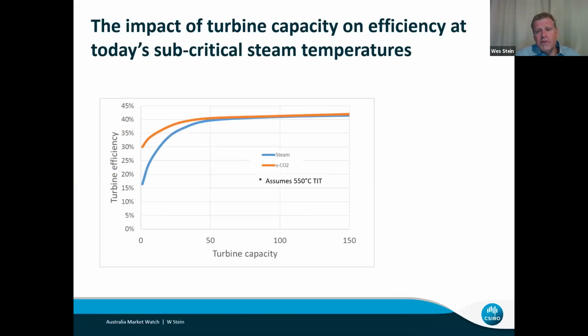One of the reasons we're interested in this supercritical CO2 cycle is that much of Australia's CSP market lies towards the edge of the grid. And there's quite a lot of opportunity for power station sizes around about the 25 to 50 megawatt capacity. Now, steam turbines typically don't like to go much below 50 megawatts. As you can see from this graph, at a 550 degrees turbine inlet temperature, the steam turbine efficiency drops down quite markedly as you get below 50 megawatts. But the supercritical CO2 cycle at 550 degrees retains its efficiency down to around about 10, 20 megawatts, which is a capacity of choice for us.